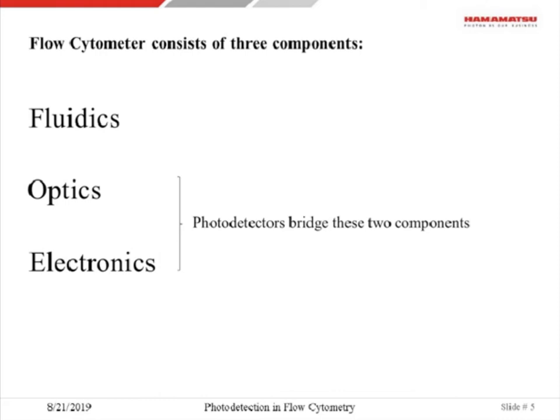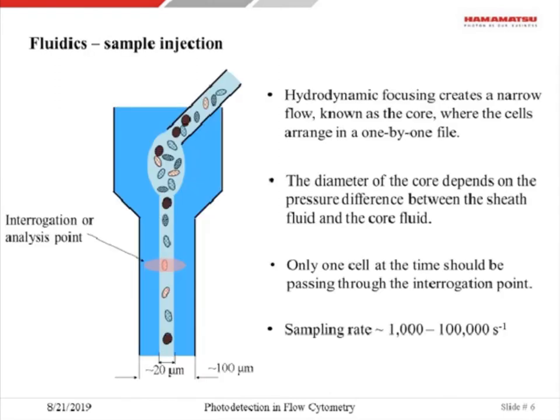A modern flow cytometry system consists of three fundamental basic elements: fluidics, optics, and electronics. A photodetector bridges the two last components, optics and electronics. The role of a photodetector is to convert a light signal to an electrical signal. The central component—perhaps the heart—of flow cytometry is the flow cell. In the flow cell, we have a sheath fluid flowing, shown in deep blue. Into that sheath fluid, a different fluid with cells suspended is injected. Due to hydrodynamic focusing, the cells in the flow are organized in a file.